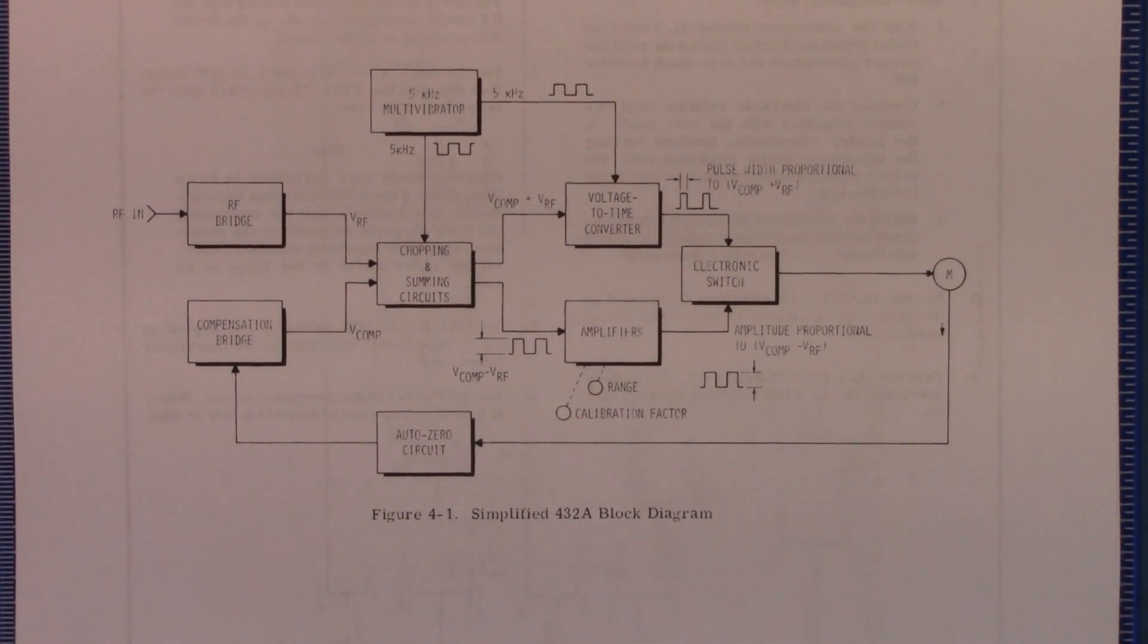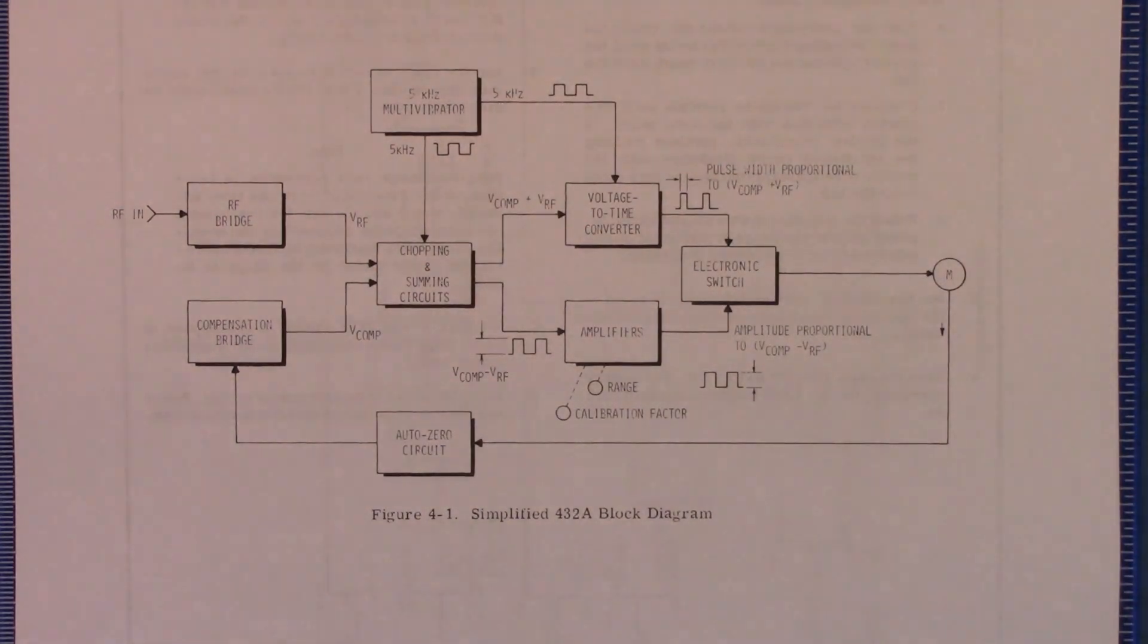Well, here we have the simplified block diagram. And what this unit is, is basically the meter part here and then a thermistor mount that looks around or splits out this part here. Those thermistor mounts are typically these guys here. This is a 478A thermistor mount. And basically what those thermistor mounts have are two thermistors in them.